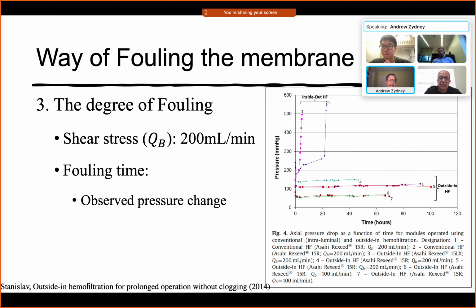So the data that's shown here are not the pressure drop across the membrane. It's the pressure drop across the filter, from the blood inlet to the blood outlet. And the reason that the pressure went up is not what I would usually think of as membrane fouling. Yes, it was actually clogging of the fibers, that's correct. That probably would not happen with BSA, but happens with blood.